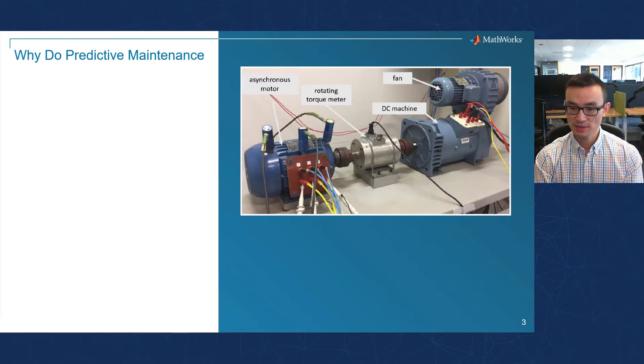There could be different types of faults occurring on those motors throughout their life cycles. Some faults, such as winding faults, like short circuit, will lead the motor to break down immediately. Some other faults, like broken rotor bar faults, for example, will cause gradual degradation of the motor. So having one of those rotor bars broken does not break down the motor immediately, but it will induce things like overcurrents in other rotor bars inside the motor and then cause them to deteriorate and eventually fail. So as an electrical engineer, I'd like to detect those faults early when it happens and to provide sufficient lead time for motor repair or replacement. And that's why we do predictive maintenance.